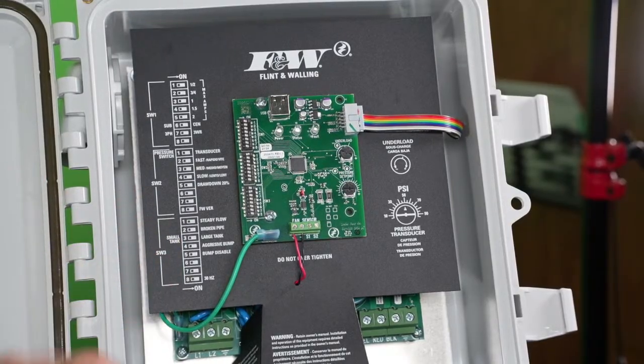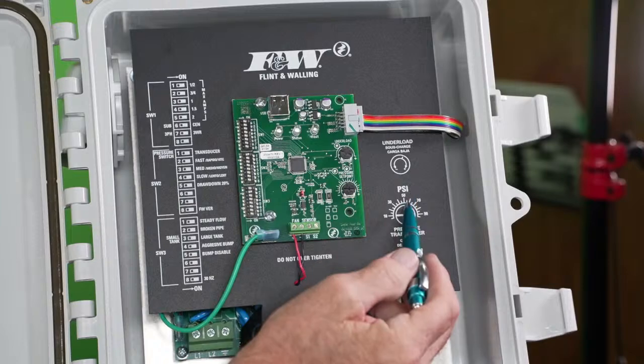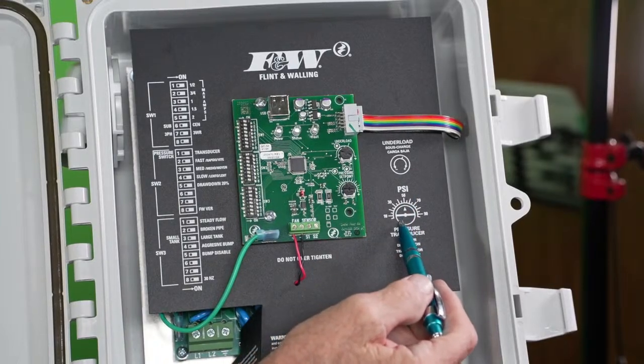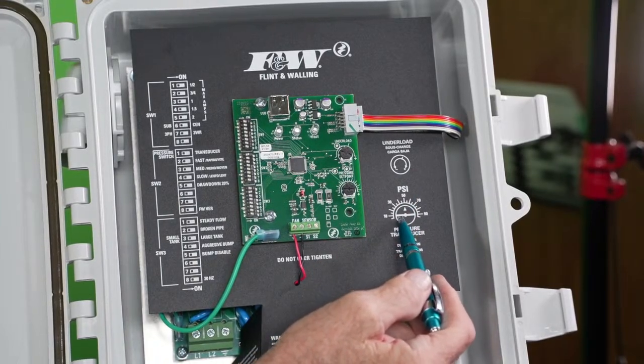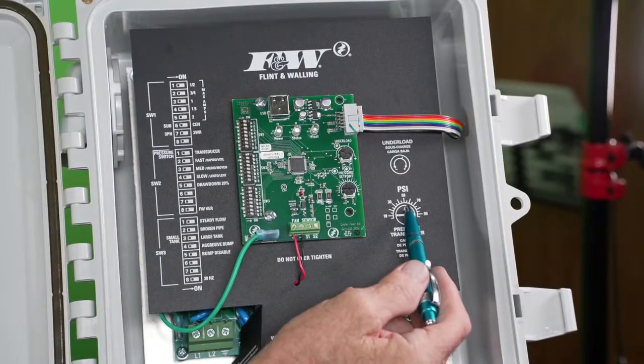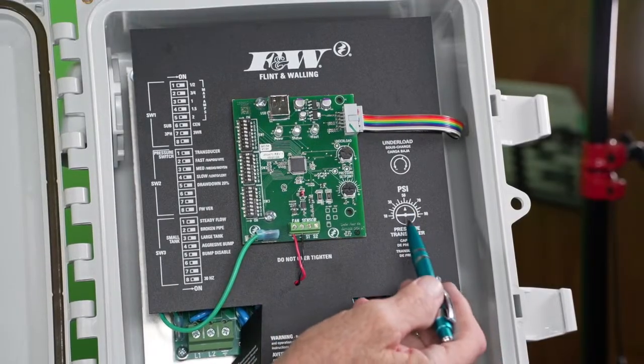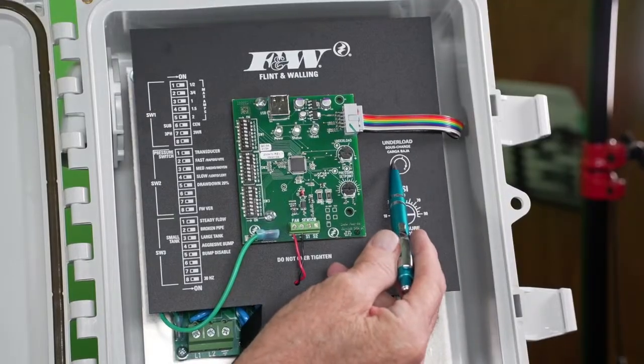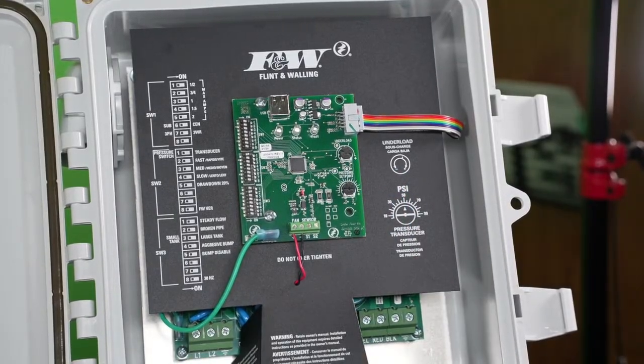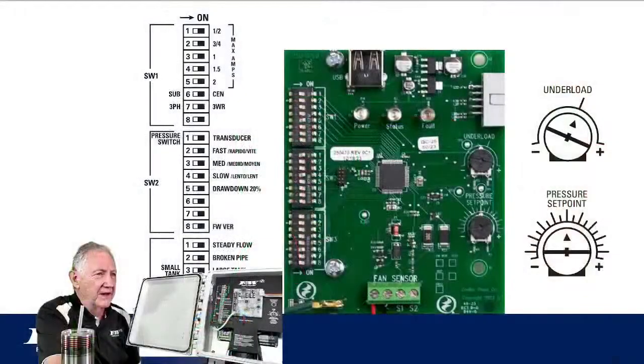So in addition to the banks on the left-hand side of the drive, you've also got 2 dials over on the right-hand side of the drive. The one on the bottom is to set a pressure set point for a transducer, and again, we're going to clarify all this in just a second. And the one at the top is for underload sensitivity. So those are 2 dials that are adjustable inside that drive. I'm going to move on to that next slide because I believe, let's see what I've got coming up here. Oh, okay.